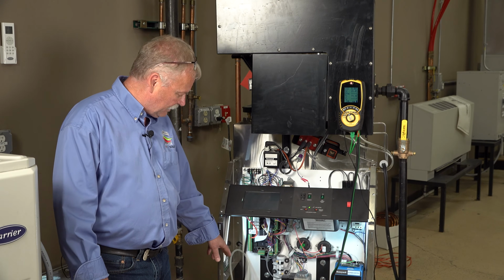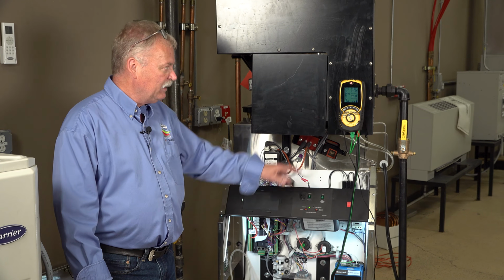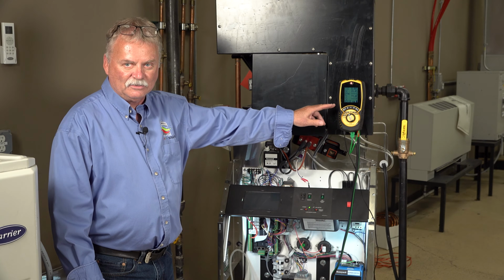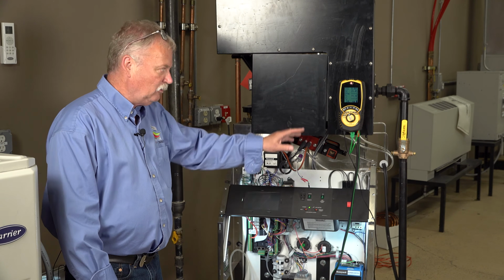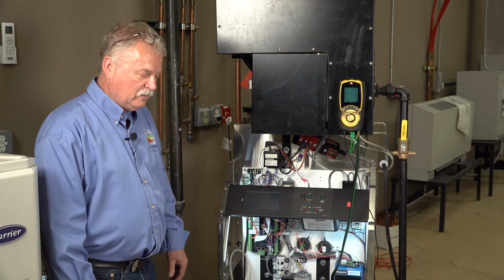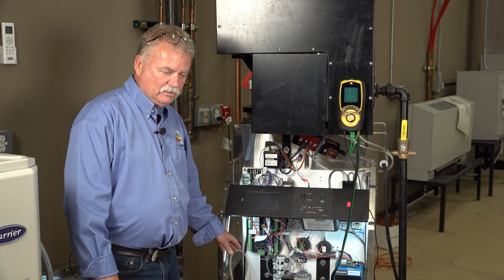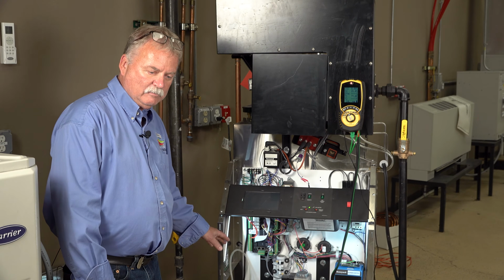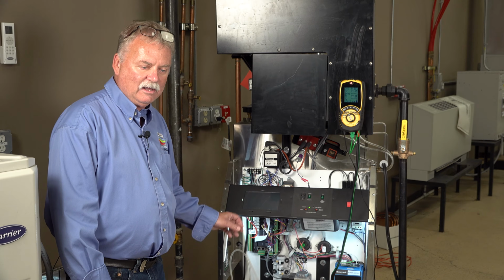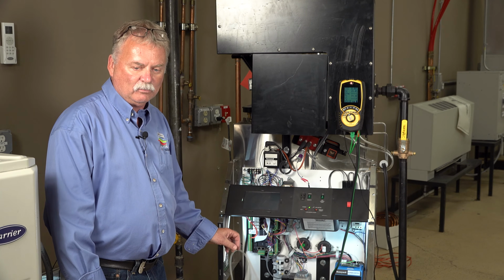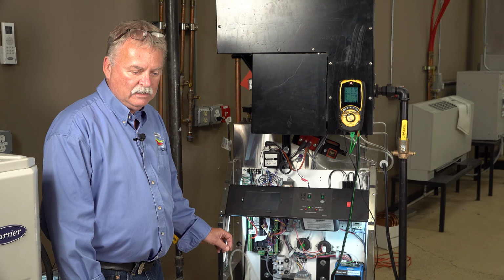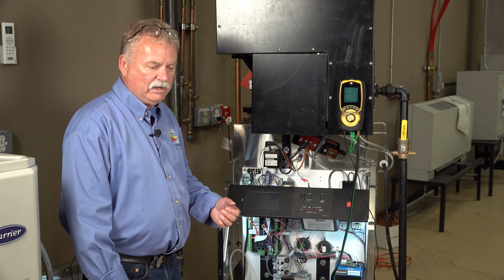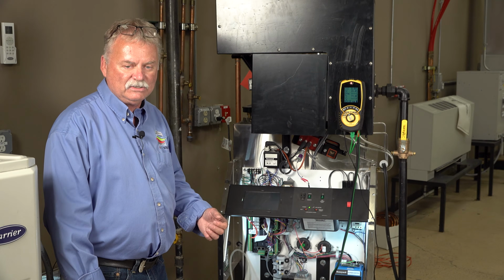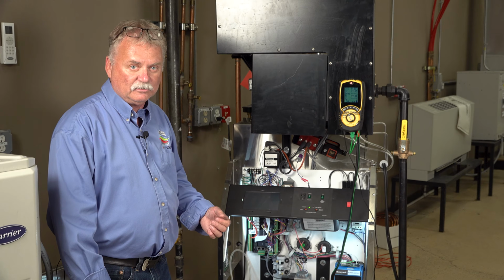I've got my gas meter here, and right up here I've got my combustion analyzer. They've both been on, looking at what's going on in the system. Basically, we want to know that we have the correct amount of gas coming in at the right pressure to the system. For this boiler, they're looking for anywhere between 3 and 12 inches incoming gas pressure.